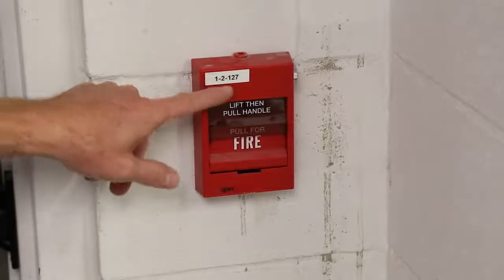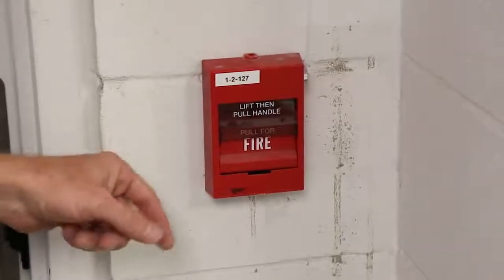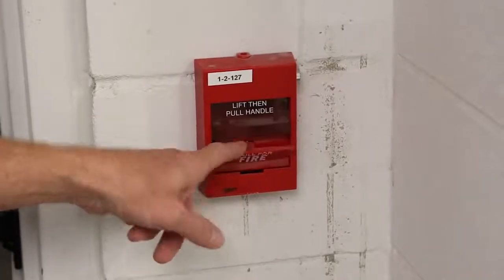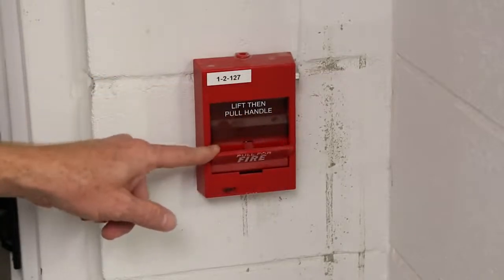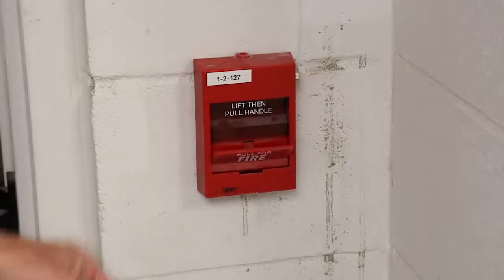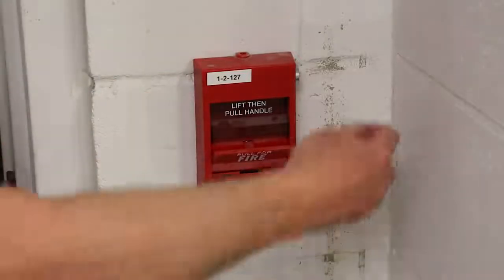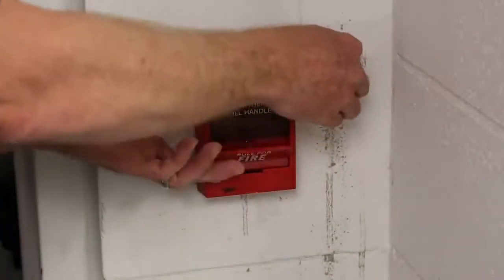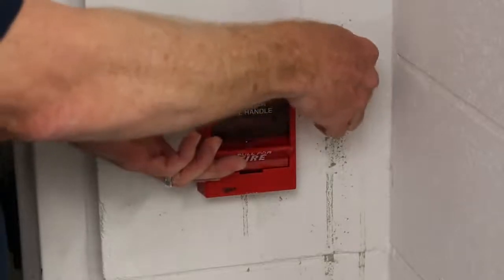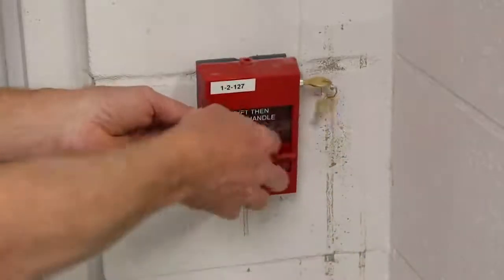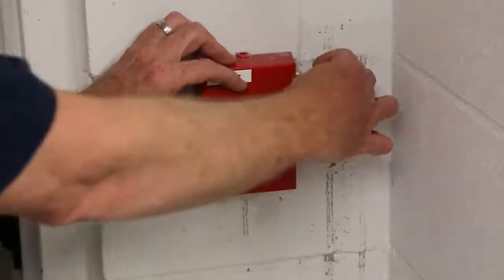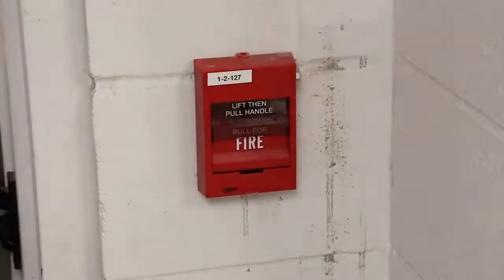We can go to a device later. All right, in the pull stations, basically we have the address label we were talking about right here for the device number. If the pull station is tripped, you'll basically see the handle sticking out like this. If the handle's sticking out like that, you can come and see it and it'll actually tell you the location of it. You can confirm the address. To reset it, remember the panel will not reset when a pull station is active. You have to reset the pull station first. Just stick the key in it, open it up, flip your switch back down, reorient the cover, just shut it back up, and then go ahead and reset the panel.